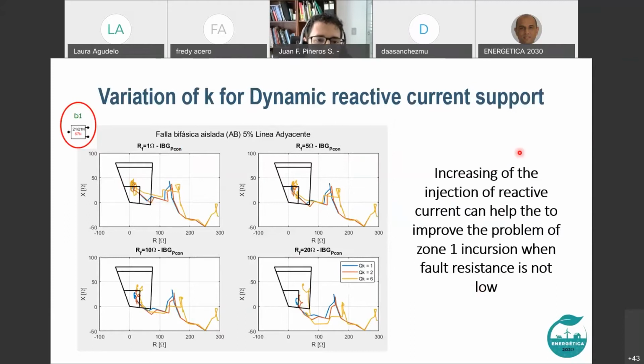Another topic we were observing is what happens when we vary the dynamic reactive current support. Normally, we started checking with the value of k equal to 1. When we increase this injection of reactive current support during a fault, we observe that with a low resistance fault the change is not so large. It means it's not important. If we have a 0 ohm or 1 ohm fault, changing how much reactive support you provide during the fault does not have a big impact. But when you increase the resistance of the fault, it helps to have a higher k value, I mean a bigger injection of reactive current support.